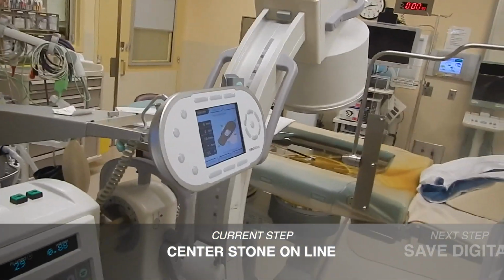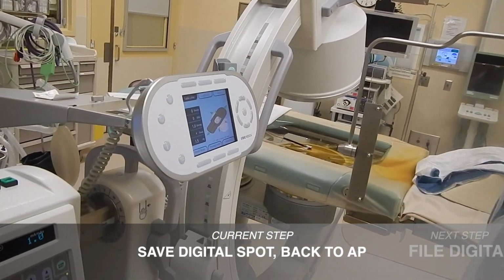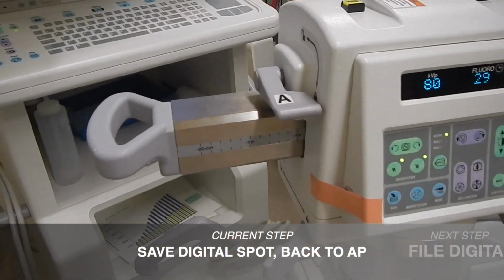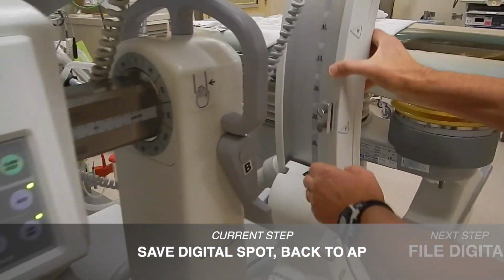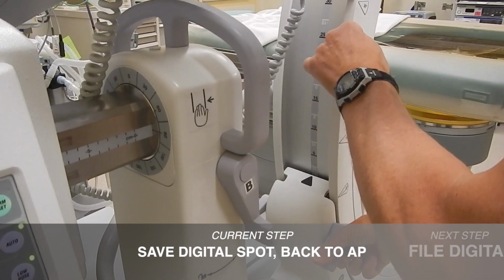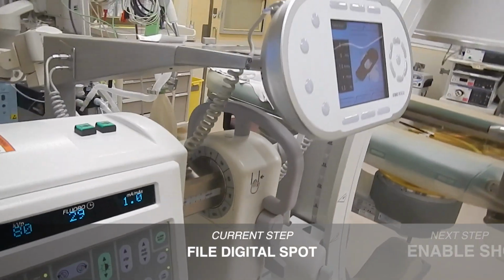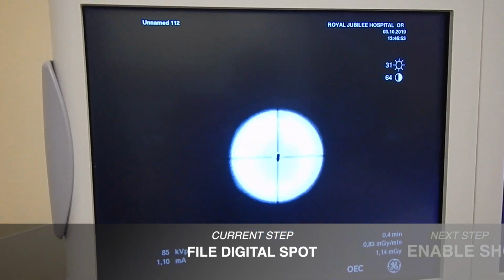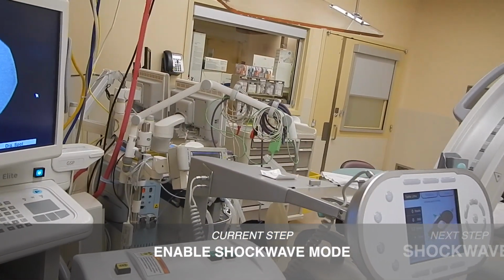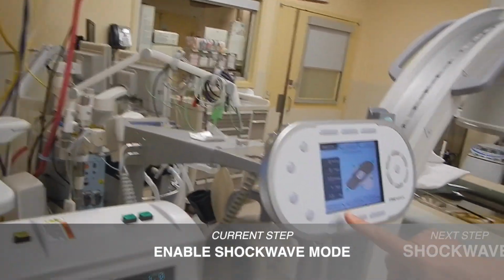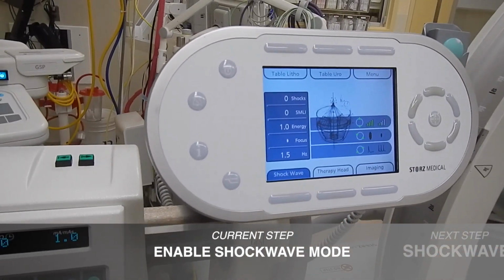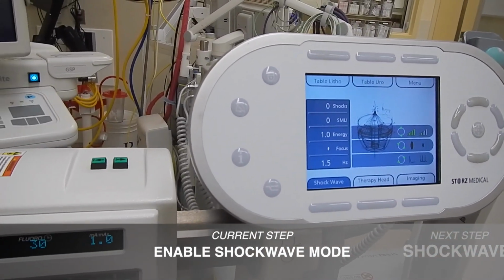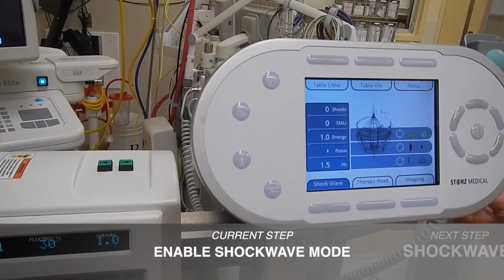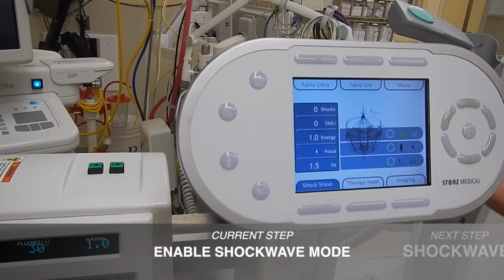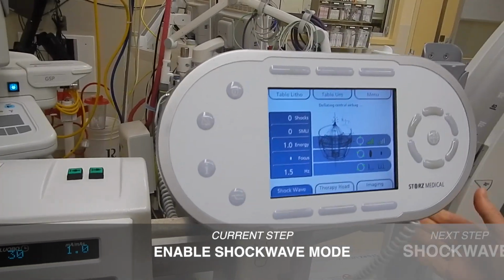We're ready. So you would save that one, go back to AP, gently lock that, always check again, make sure you don't need any more adjustment. And then basically the tech makes sure that shockwave mode is enabled, and now the urologist will come in and initiate the shock. So you just lift the trigger, turn it around, pull it down.